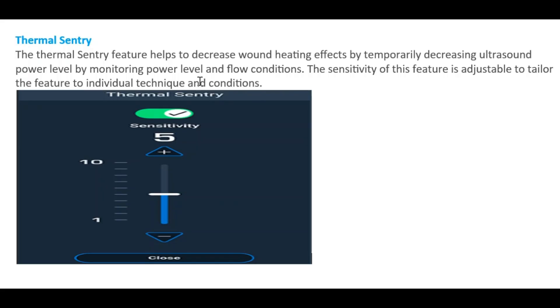Alcon has yet to release full explanations on this, as it's a very new machine. It likely works by sensing reduced irrigation flow combined with prolonged power use, indicating potential wound heating. A key question remains: since torsional power may cause less wound heating, will this feature also activate during prolonged torsional use with reduced irrigation flow cooling the phaco tip?